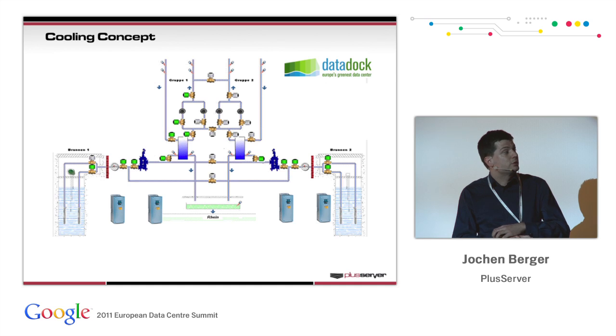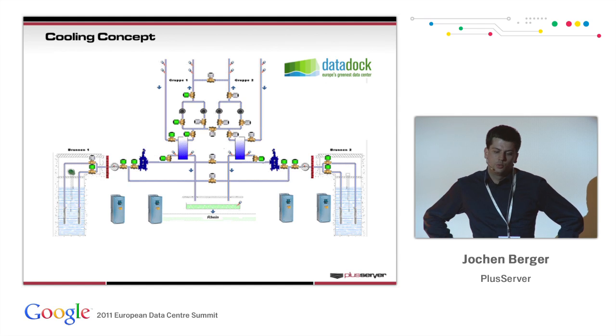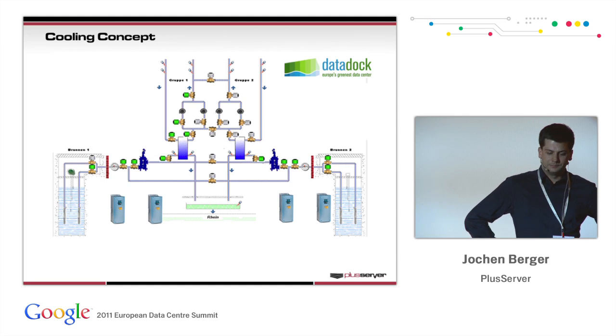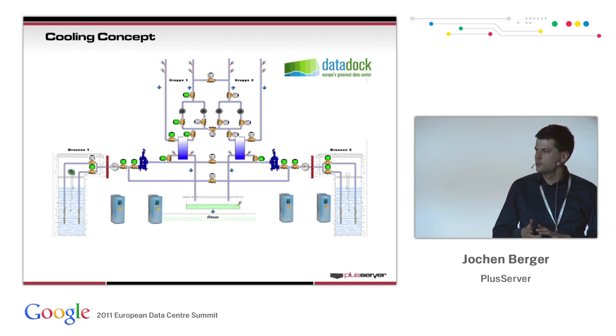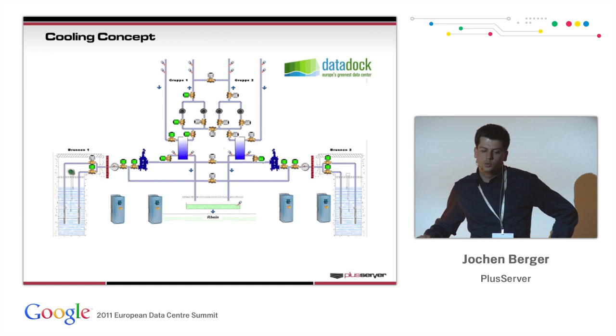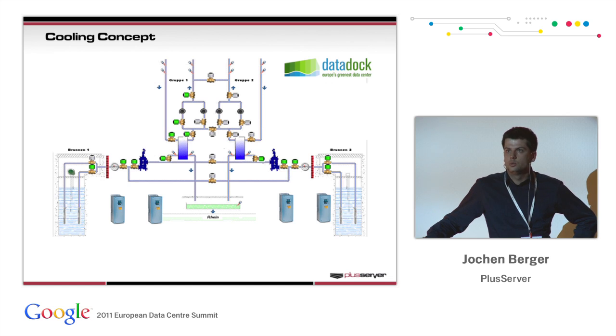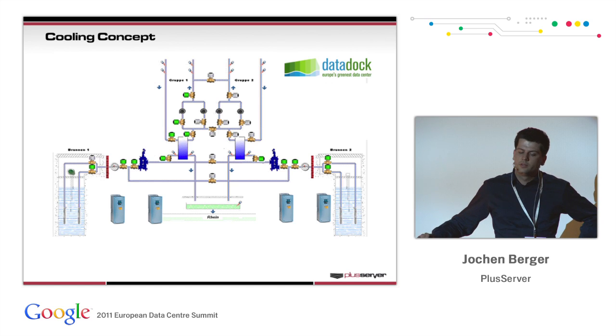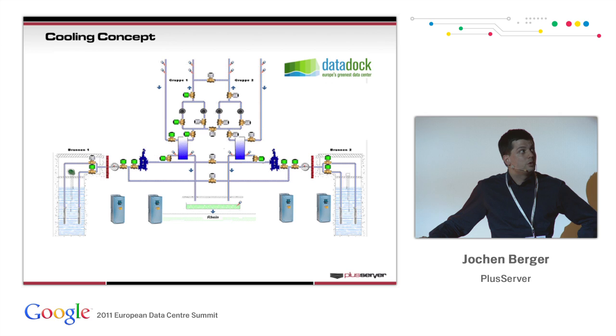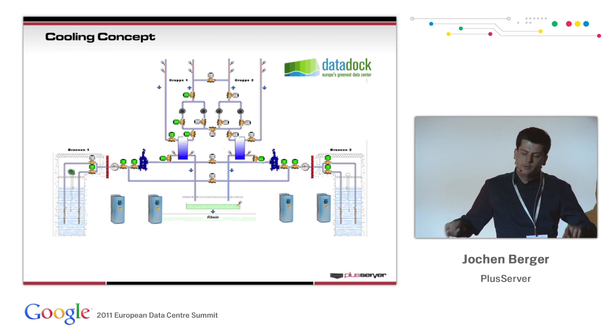Everything is built redundant, so we always have 2 ways to each heat exchanger. We have 2 ways in order to go to our CRAC units. Everything is fully redundant, so that we can go from one circle to the other without getting any failure. Besides the groundwater cooling, we don't have any additional cooler, so we have no other cooling equipment. We are fully reliant on the groundwater, and that's why everything is redundant.